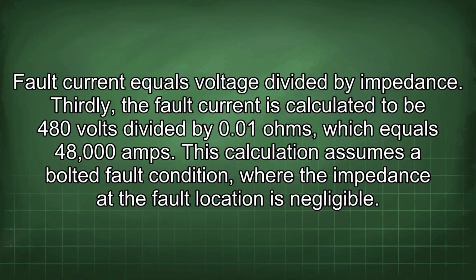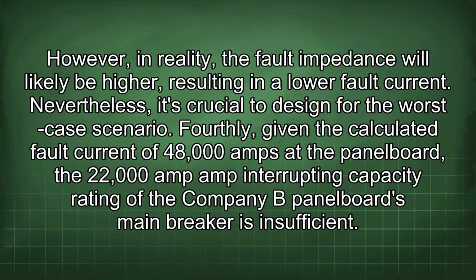This calculation assumes a bolted fault condition, where the impedance at the fault location is negligible. However, in reality, the fault impedance will likely be higher, resulting in a lower fault current. Nevertheless, it's crucial to design for the worst-case scenario. Fourthly, given the calculated fault current of 48,000 amps at the panel board, the 22,000 amp interrupting capacity rating of the company B panel board's main breaker is insufficient.